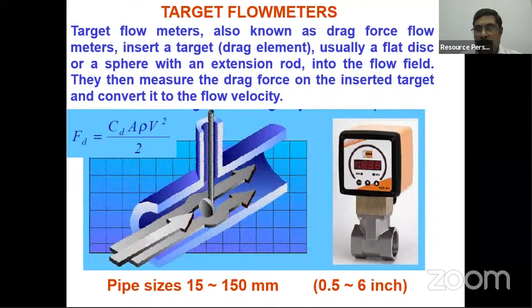So when the flow takes place, the flow will hit the target. It will produce a kind of strain which is measured by the strain gauge. By measuring the strain, the drag force can be measured. From the drag force, the unknown velocity can be measured. From the velocity, you can get the flow rate. Again, the pipe size can be from ½ inch up to maybe about 6-inch diameter. Sensitivity is also reasonable. Accuracy also, but accuracy depends on how well you calibrate the instrument.